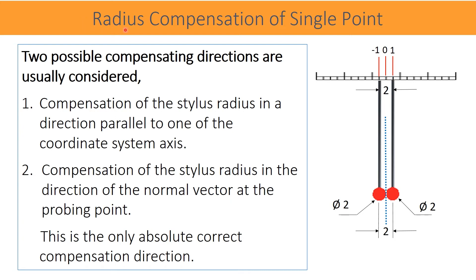Radius correction by offset of the geometry profile is very easy. But this logic is not applicable or does not work for single point measurement. There are various applications in measurement where we need to measure a single point. For such single points, radius compensation can be in all 360 degree directions. If the exact direction of compensation is not known, it is very difficult to determine in which direction the point is to be compensated.